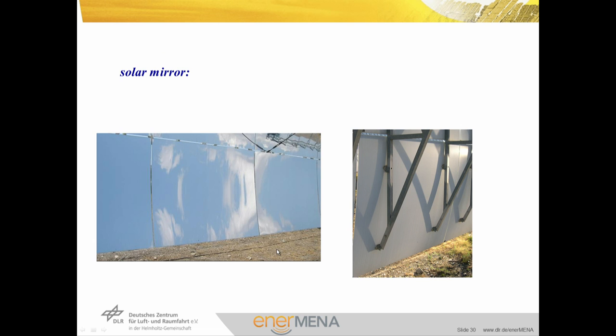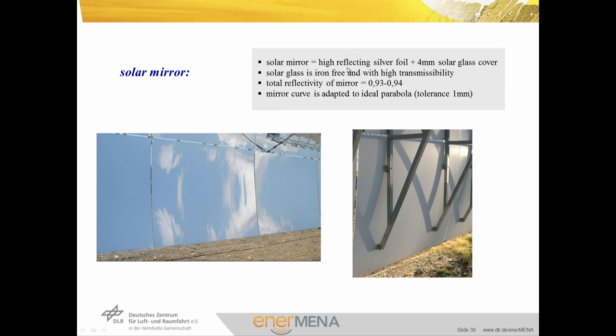The solar mirrors are highly reflective silver foils with a 4 mm solar glass cover. The solar glass is iron-free with high transmissibility. The total reflectivity of the mirrors is 0.93 to 0.94. The mirror curve is adapted to the ideal parabola with a tolerance of 1 mm, and it is very important that the cantilever arms are assembled inside a special jig to give the final correct position of the mirrors.